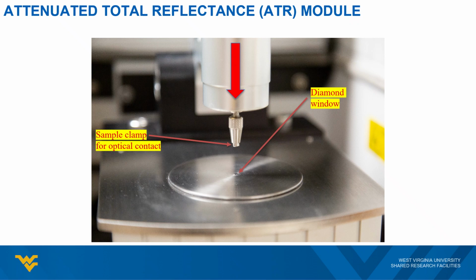Here, we are taking a closer look at the ATR module of our FTIR instrument. During a measurement, your sample should be applied directly onto this small diamond window. Next, the sample clamp must be securely closed. This action ensures good optical contact between the sample and the window, a crucial factor for achieving accurate results. The IR beam will be introduced from the bottom of the window. Upon encountering the sample, the IR beam reflects, carrying information about the absorption property of the sample. This reflected light is then collected and analyzed by the detector. The resulting spectrum is then ready for further analysis.